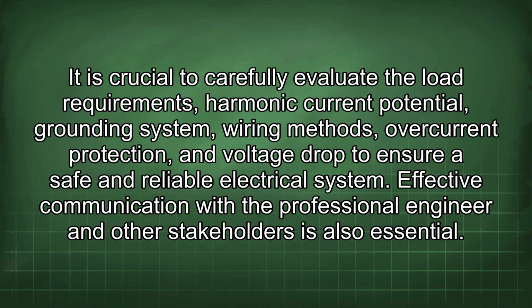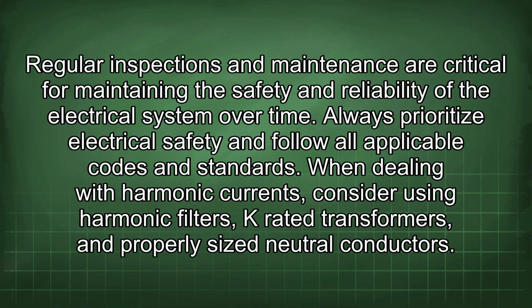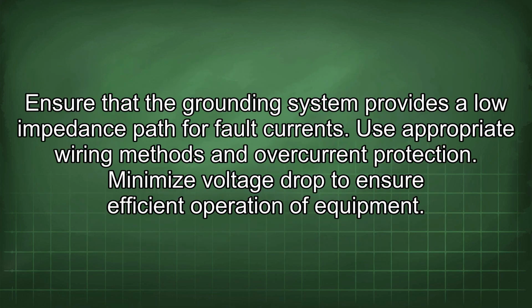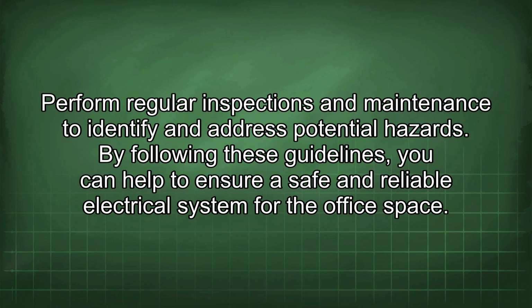Effective communication with the professional engineer and other stakeholders is also essential. Regular inspections and maintenance are critical for maintaining the safety and reliability of the electrical system over time. Always prioritize electrical safety and follow all applicable codes and standards. When dealing with harmonic current, consider using harmonic filters, K-rated transformers, and properly sized neutral conductors. Ensure that the grounding system provides a low impedance path for fault currents. Use appropriate wiring methods and overcurrent protection. Minimize voltage drop to ensure efficient operation of equipment. Perform regular inspections and maintenance to identify and address potential hazards. By following these guidelines, you can help to ensure a safe and reliable electrical system for the office space.